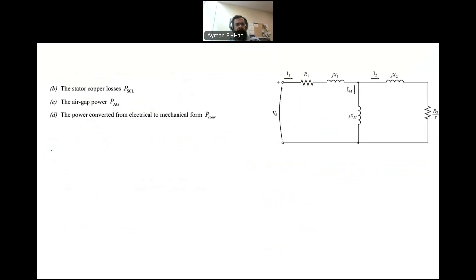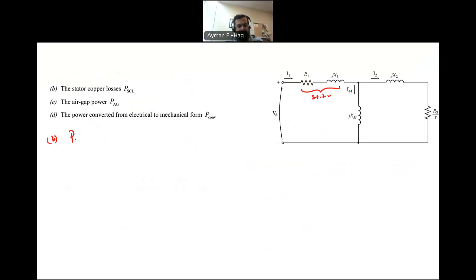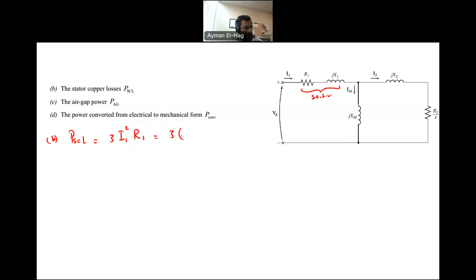For Part B, we want to find the stator copper losses. The stator copper loss equals 3 times I1 squared times R1 — the factor of 3 accounts for three phases. So this is 3 × 78² × 0.1, which gives total stator copper losses of 1,825 watts.